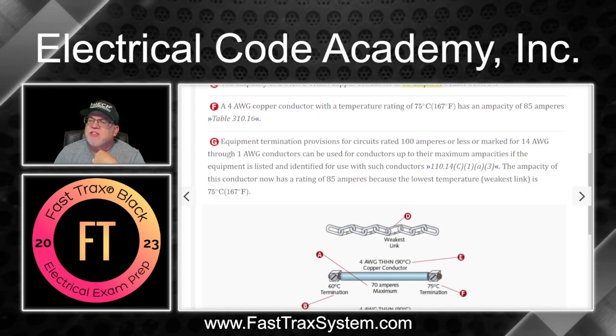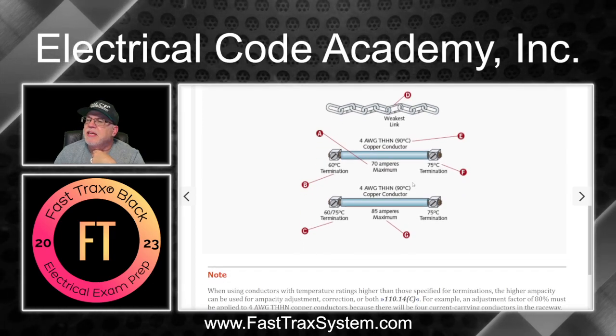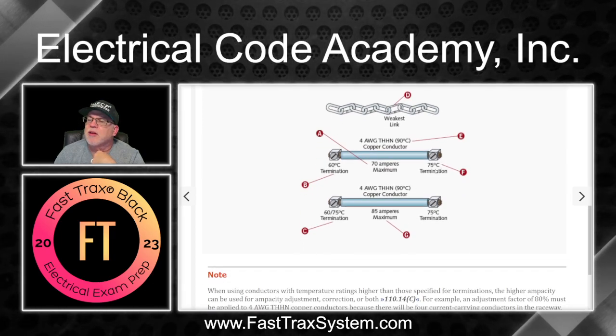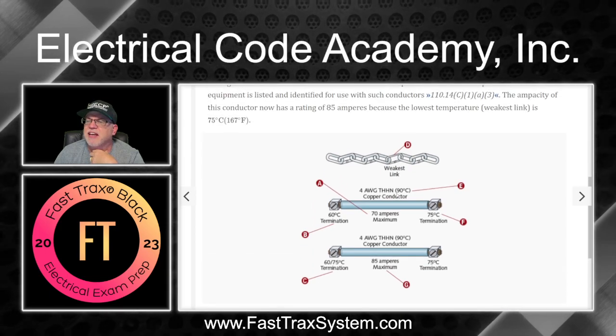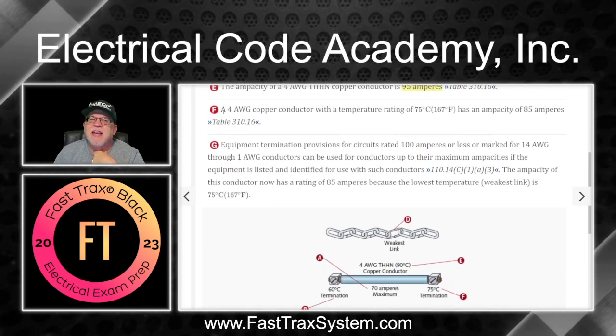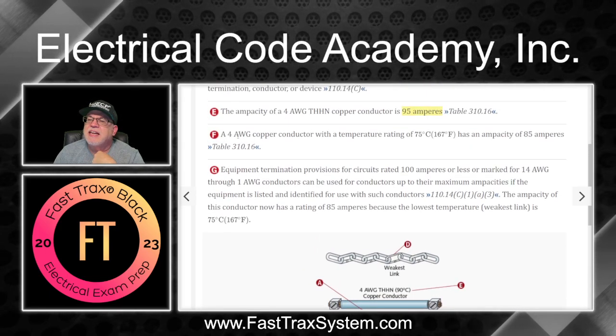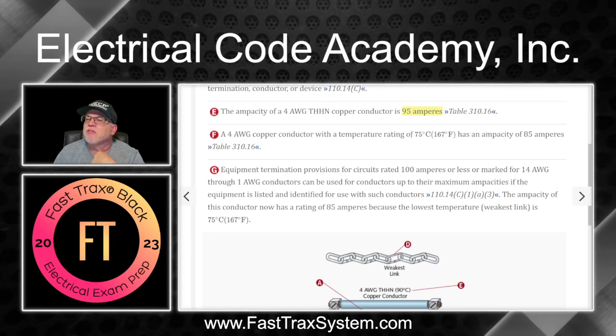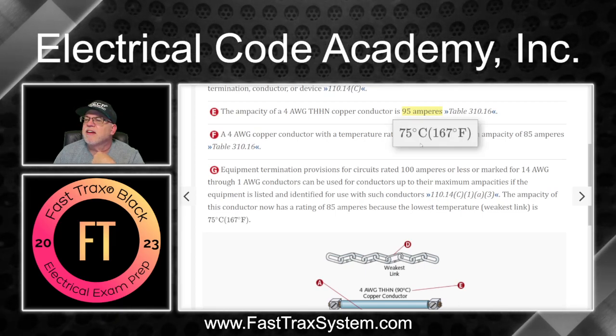All right, next is F. F being, I guess, right here. So this is the terminal at the equipment end, let's just say. It says a 4 AWG conductor with a temperature rating of 75 degrees C has an ampacity of 85.